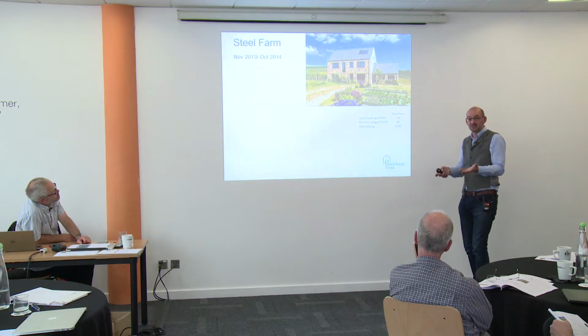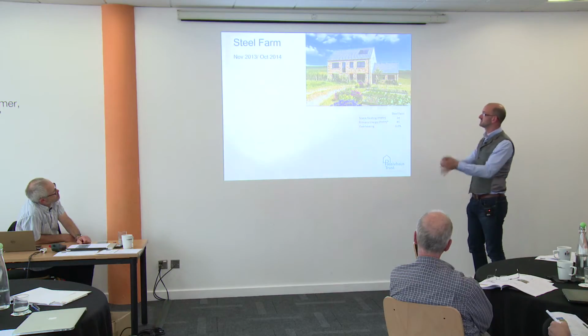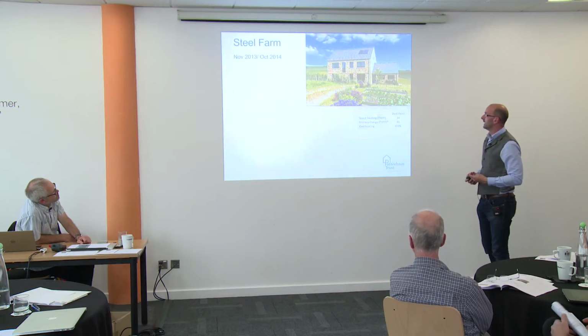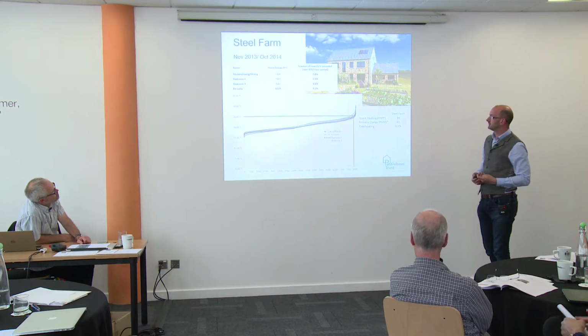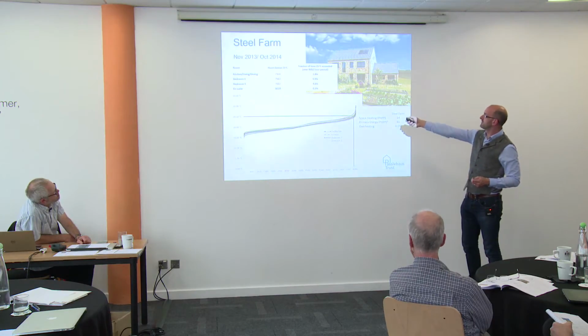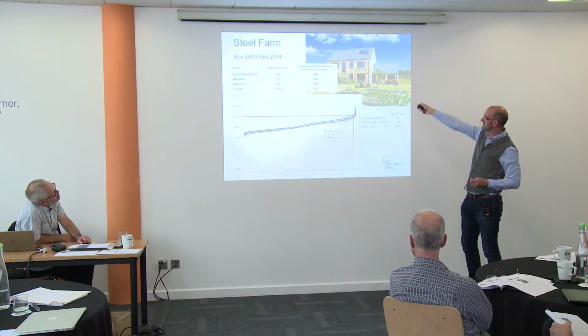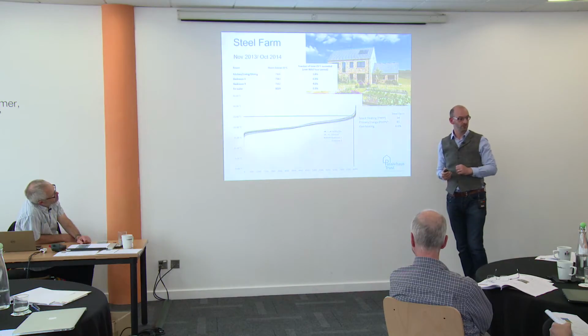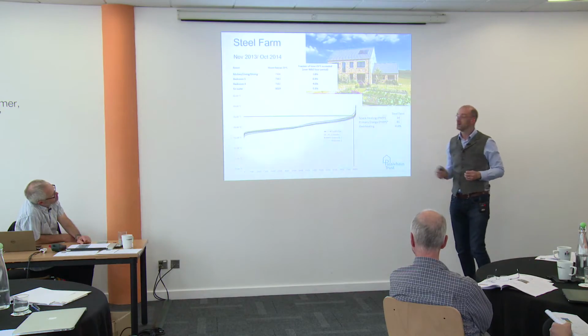So what's the reality? I got some data logs and threw them in the house for 11 months. And this is what we started to find out: the kitchen, living, dining area, down on the ground floor over here, goes above 25 degrees Celsius for 1.8% of the year. Bedroom number 3, this room here, went over 25 degrees Celsius for 4.6% of the year, but there was nobody in there to open the windows because it's an unoccupied room.